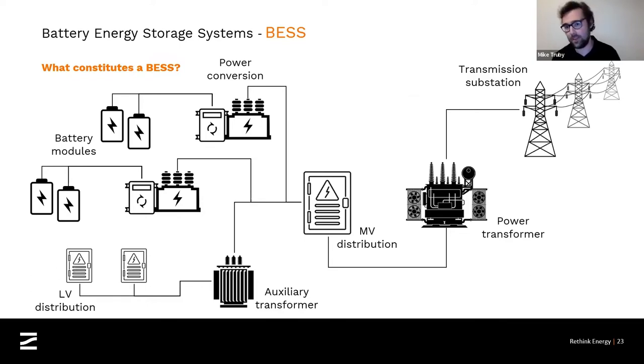This is 275 kilovolts, and I'll talk in a little while about why that is. And because it's connected at 275 kilovolts, we then connect through a power transformer. We can't generate power from the batteries at that kind of voltage, and so we need some kind of step-up transformer to connect it to the grid. We then have an MV distribution system on the site. We tend to generate power in the batteries, or charge and discharge the batteries, at a low voltage. We'll come on to how that works in just a moment. And then we transform it up to a medium voltage, typically 11 or 33 kV, to distribute it around the site. We do that to manage losses, basically.